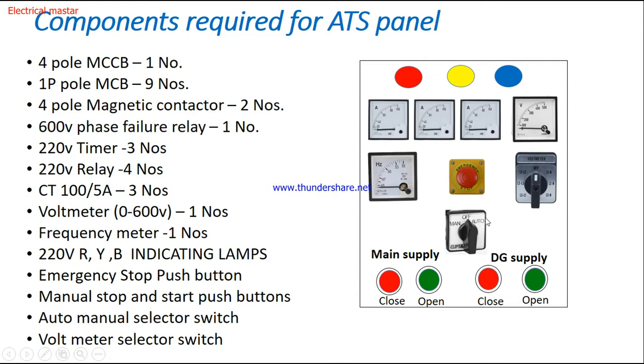If we put the auto mode, the ATS panel will sense source 1 — the electricity supply. Whenever the electricity supply is not available, it automatically changes the load to the diesel generator supply. Similarly, when the electricity supply comes back, it changes the load back to the electricity supply and switches off the DG.